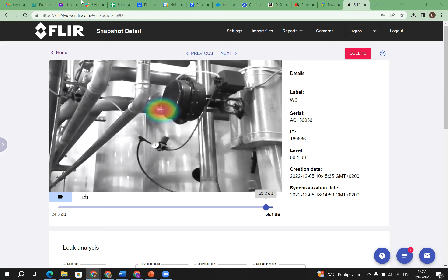Then I will just show the partial discharge, which is maybe one of the most interesting things. Let's go first to a very harmless partial discharge. You see here, we found this partial discharge, which was audible. I remember that we could listen to it. You see the PD there, right? So the camera is showing it. The analytics show the type of partial discharge: it was a negative corona, which is often harmless, with a little bit of positive and negative, because these phenomena are not 100% classified. They are often a mixing of phenomena, a little bit of floating, a little bit of positive corona.